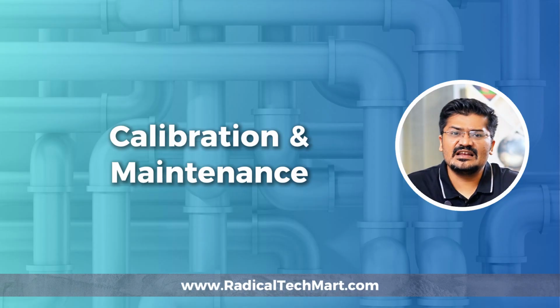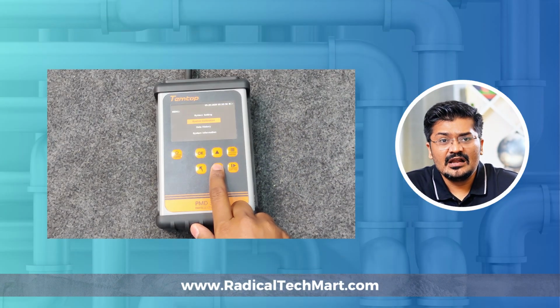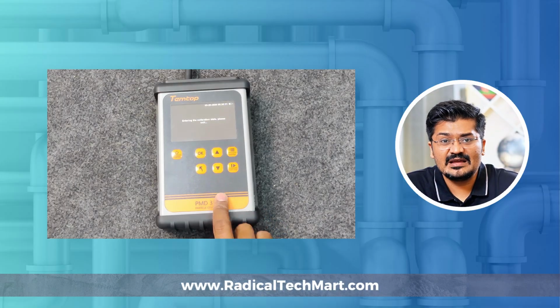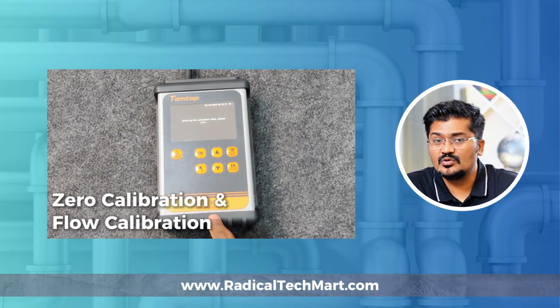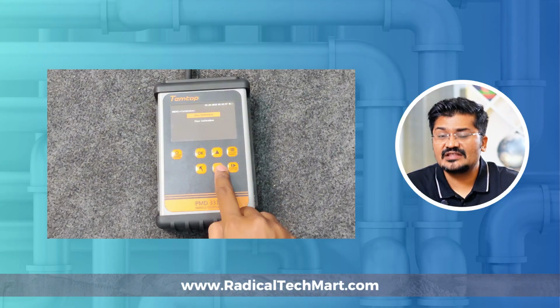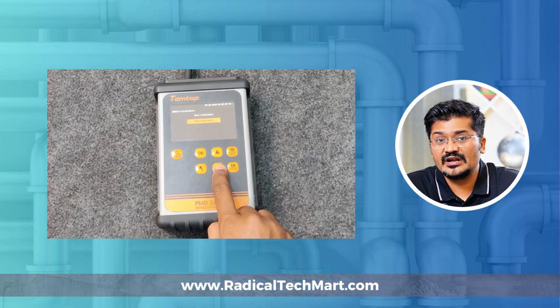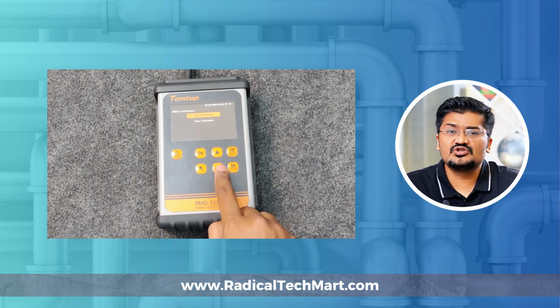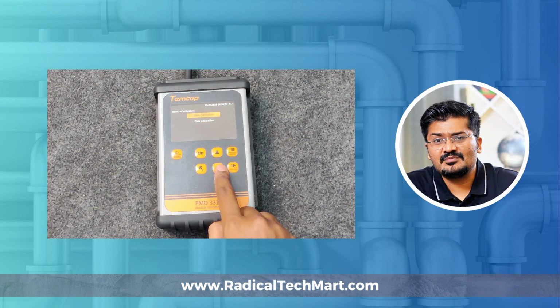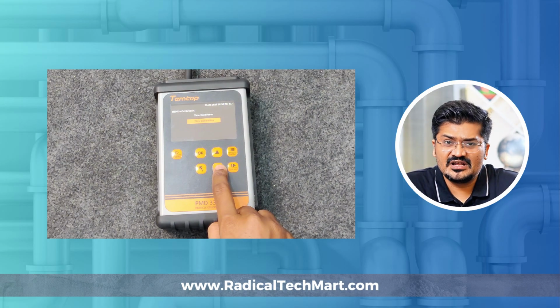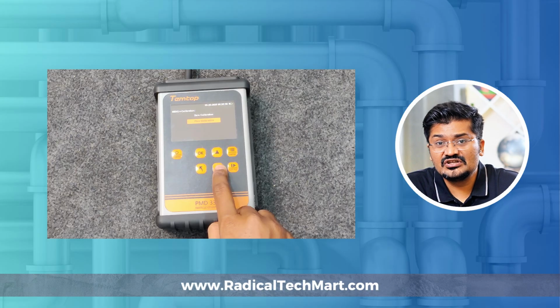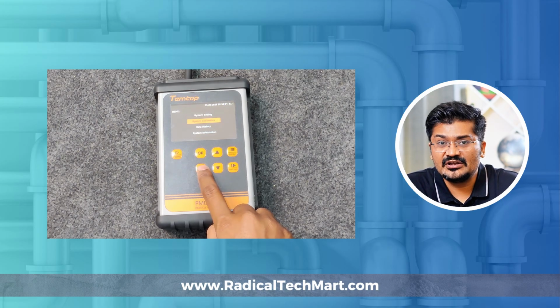Now, let's understand calibration and maintenance. For better reliability, regular calibration is very important. The PMD 331 supports zero calibration and flow calibration. Zero calibration helps to check the instrument with clean filter air, and flow calibration helps to maintain the correct flow rate up to 2.83 liters per minute. As per particle use, zero calibration should be done regularly, especially after long use or when the operation environment changes. And flow calibration should also be checked periodically. For critical applications like clean rooms or pharma, calibration should always be done as per the official manual and company SOP.